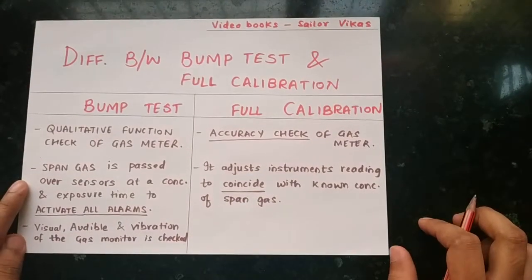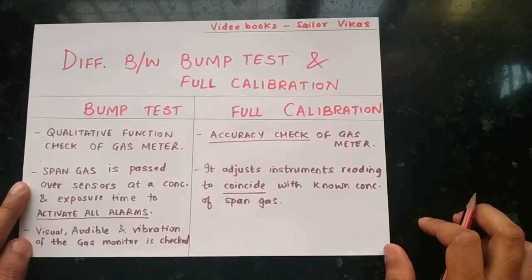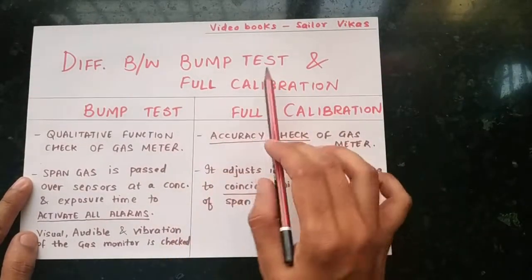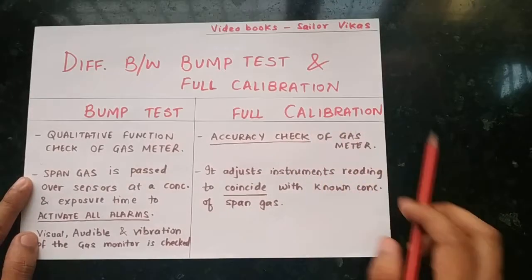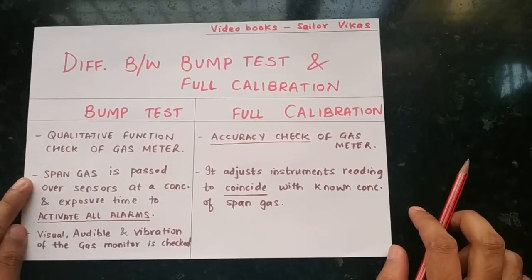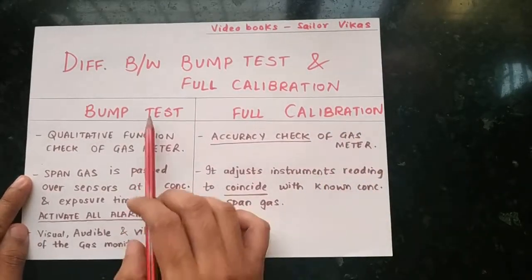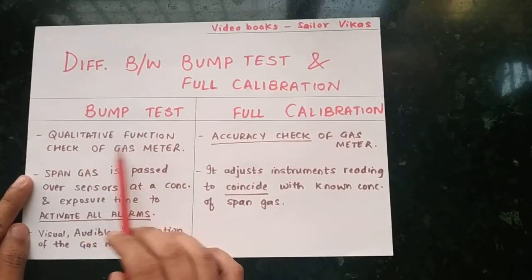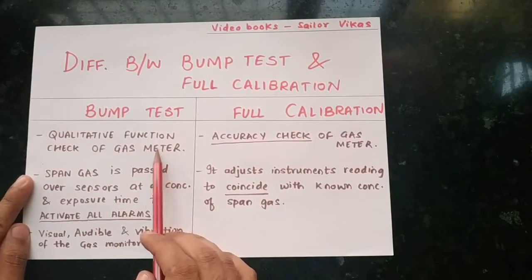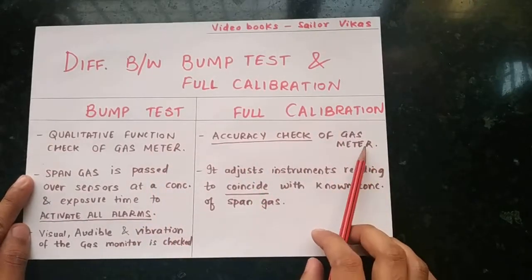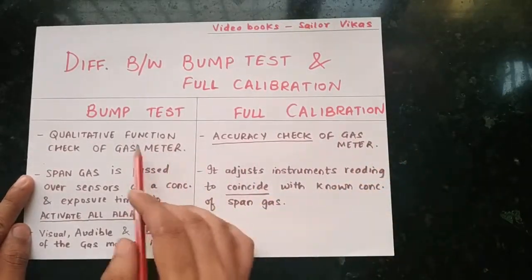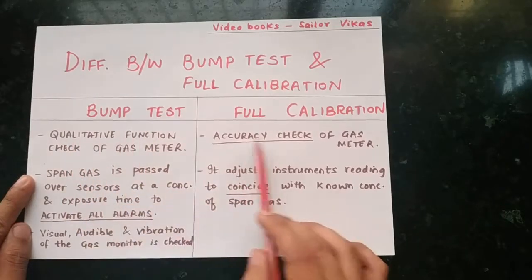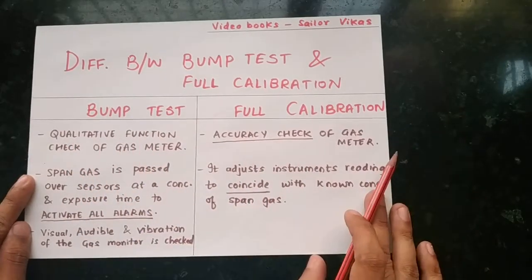This is a question recently asked in orals: the difference between bump test and full calibration in gas meters. In bump test, it is a qualitative function check of the gas meter, and full calibration is nothing but an accuracy check. So qualitative function check versus accuracy check — this is very easy to remember.